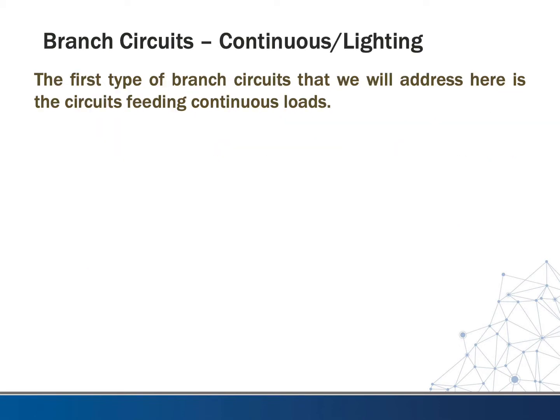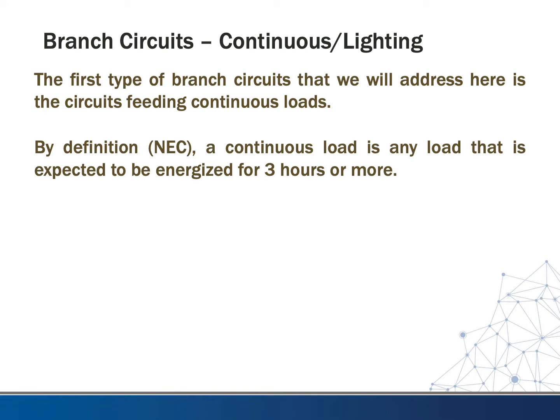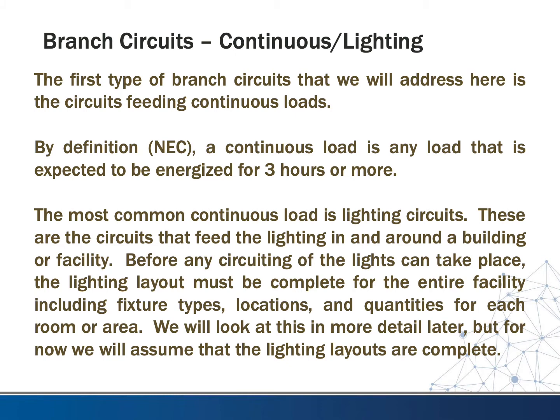The first type of branch circuit we'll address is circuits feeding continuous loads. By definition from the National Electrical Code, a continuous load is any load expected to be energized for three hours or more at a time. The most common continuous load is lighting circuits — when lights are on in an office building, they're typically on for at least eight hours or more.